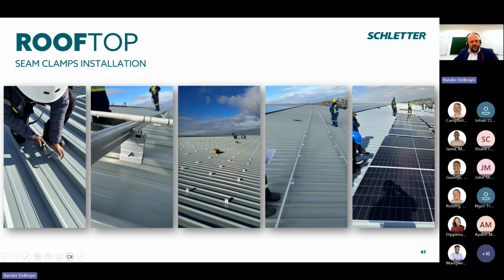Over here, I've just taken a picture of a jig that they've used to ensure that the clamps are spaced within those clamping zones that we discussed earlier. So they've just taken a piece of pipe and made marks on it to say, okay, that is 1.45 meters as per their module that they're using. And then they place the rails across and fasten. And once that's done, then they can place modules, and you can see they've clicked in the module clamps along the line where the rail was.